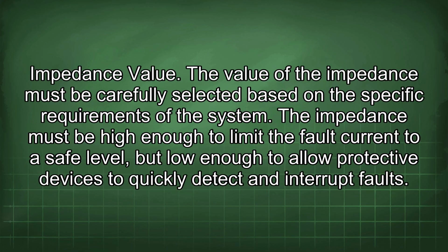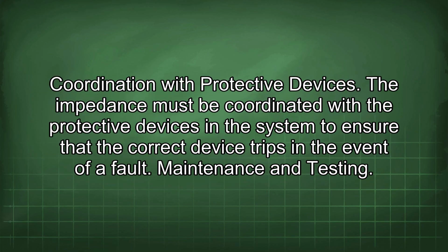Seventhly, considerations. Impedance value. The value of the impedance must be carefully selected based on the specific requirements of the system. The impedance must be high enough to limit the fault current to a safe level, but low enough to allow protective devices to quickly detect and interrupt faults. Coordination with protective devices. The impedance must be coordinated with the protective devices in the system to ensure that the correct device trips in the event of a fault.